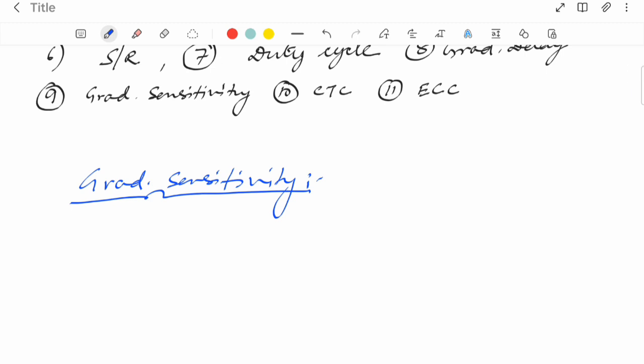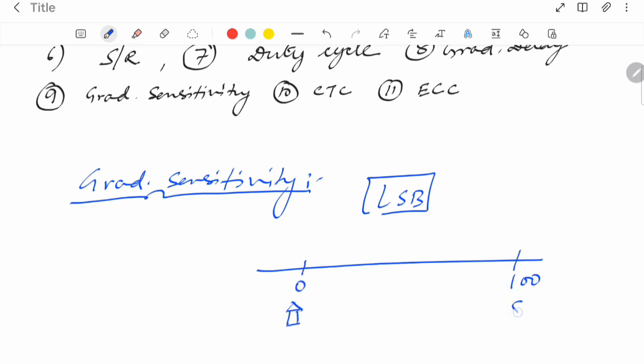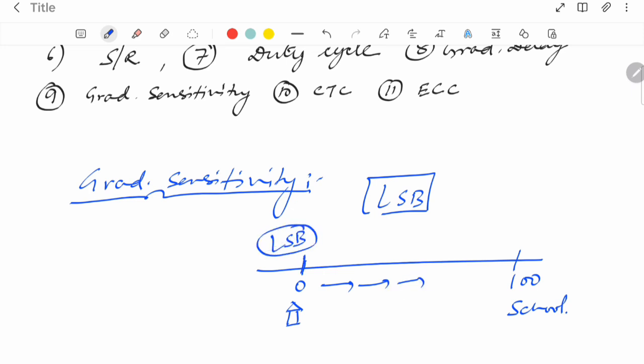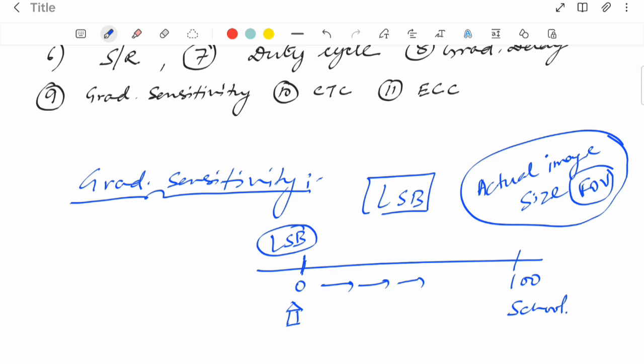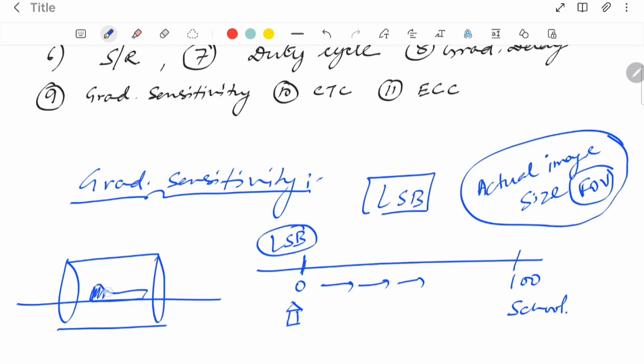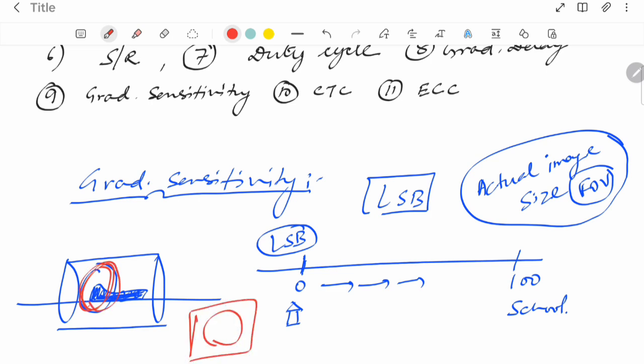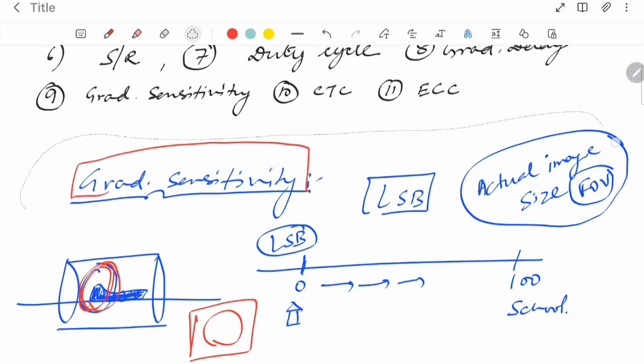Gradient sensitivity relates to fixing the actual LSB — least significant bit — of the gradient amplifier. It is mandatory to fix the LSB to calculate gradient strength, which ultimately determines the actual image size and field of view (FOV). When a patient is in the MRI and a head scan is done, gradient sensitivity helps determine the relationship between the image size and the actual patient size.